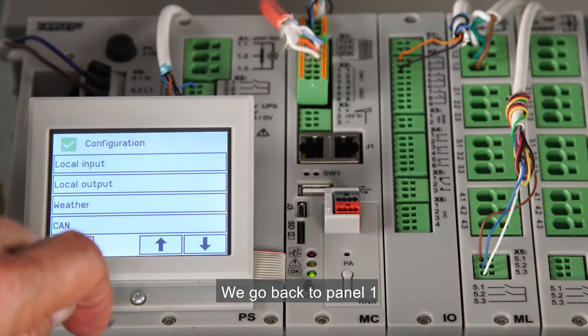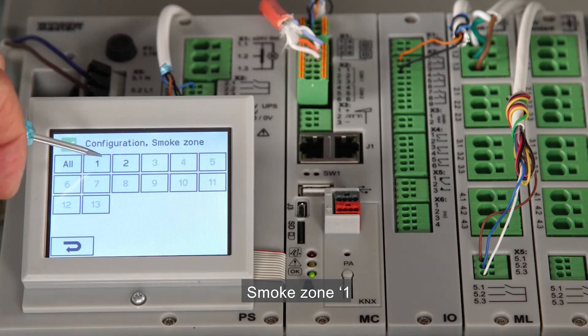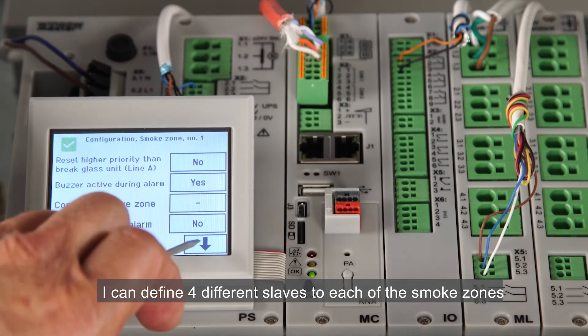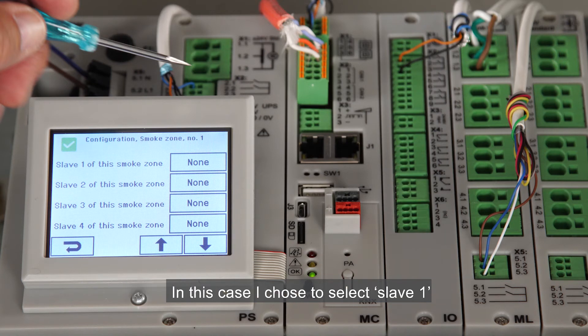We go back to panel 1. I'll now configure the smoke zone to be a master. From the configuration menu, I select smoke zone, smoke zone 1. I can define four different slaves to each of the smoke zones. In this case, I chose to select slave 1.